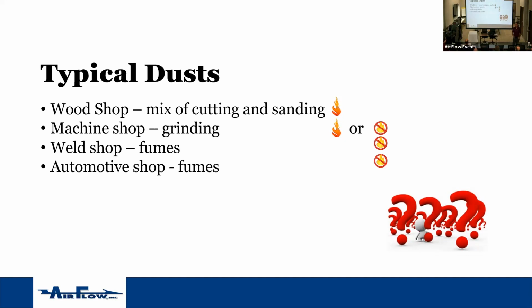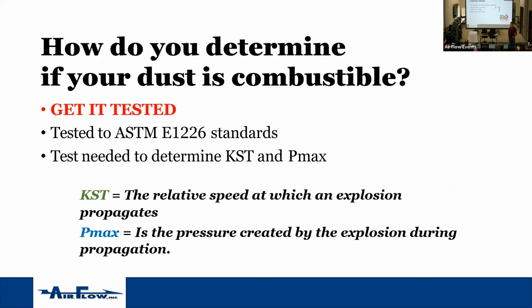We don't know. There's really only one way to find out if your dust is explosive or not, and that's get it tested. It is a very inexpensive test in practicality reasons. It's probably $300 to $500, depending on how much dust and the type of dust and the number of tests that they have. Fike will do it for you. We can get you all the information you need to send it in. Your owner, whoever's on site, whoever's the maintenance guy, actually needs to go grab a baggie, just put it in a sandwich baggie of dust, label it, mail it into Fike with the check. They probably all do it online now.